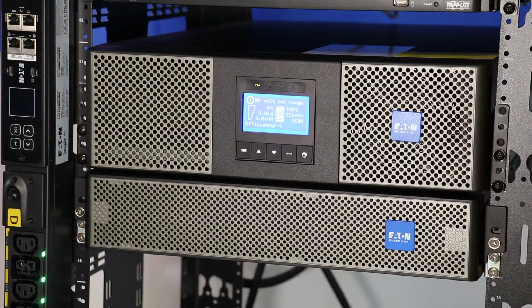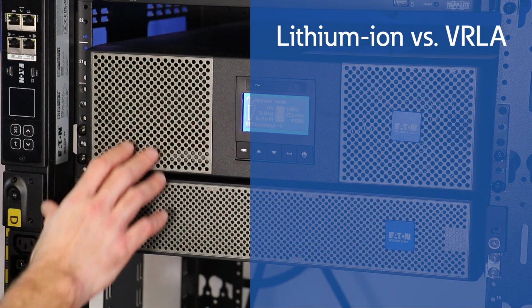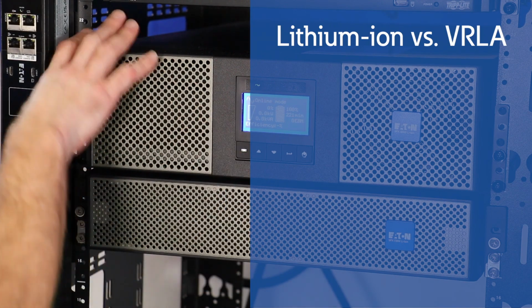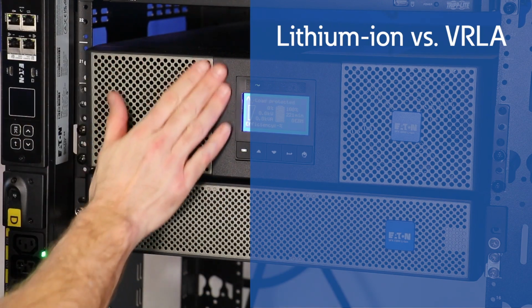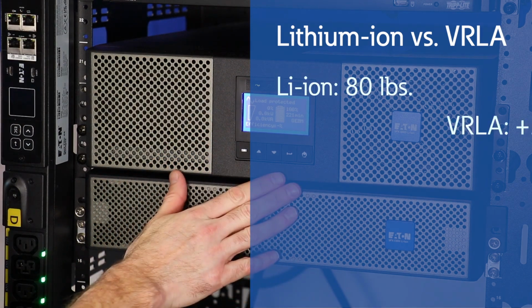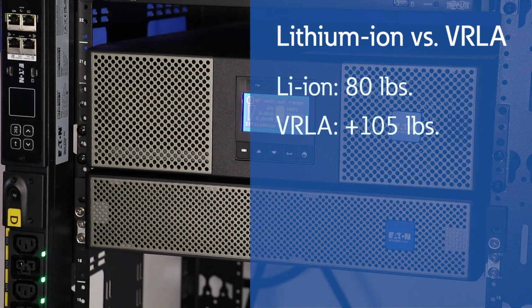Moving over to the rack, a couple quick comments. If you've installed both the new Lithium-ion UPS and the VRLA solution, there's a definite weight difference between the two modules. The lithium-ion unit weighs close to 80 pounds, while the VRLA UPS is over 105 pounds.